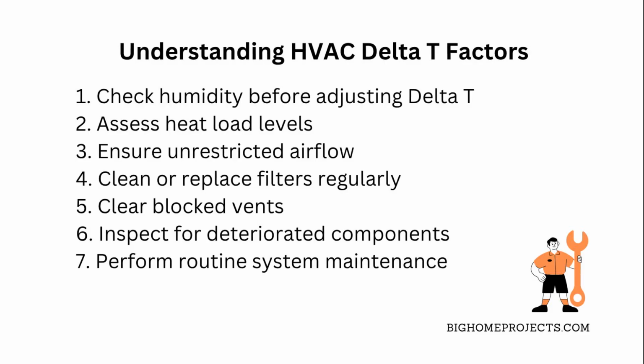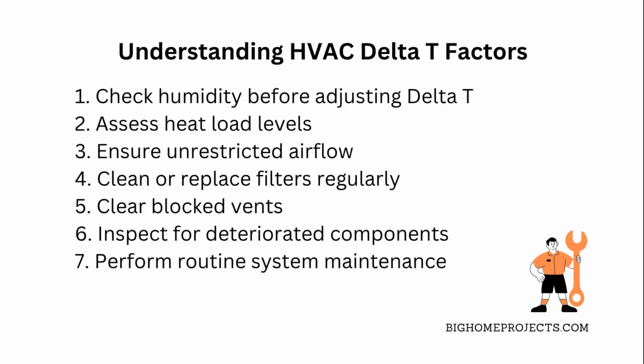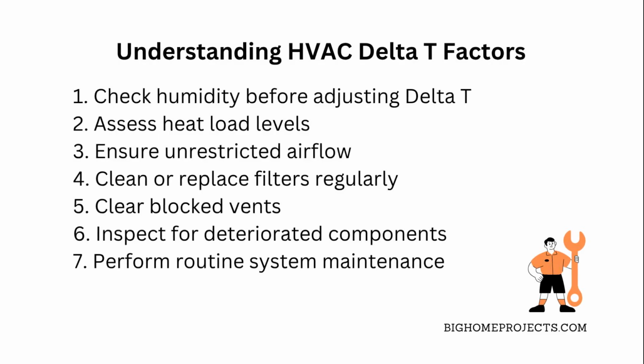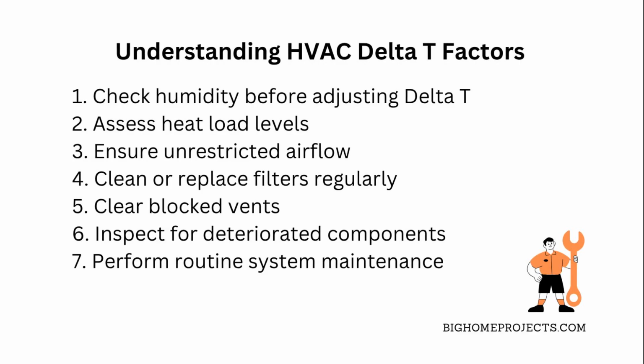If it's too low, that could mean weak airflow or refrigerant issues. Too high, and maybe your system is overcooling or airflow is restricted. But don't just rely on Delta T by itself because it doesn't tell the full story. You gotta check superheat and subcooling too, which help you understand the refrigerant charge better.